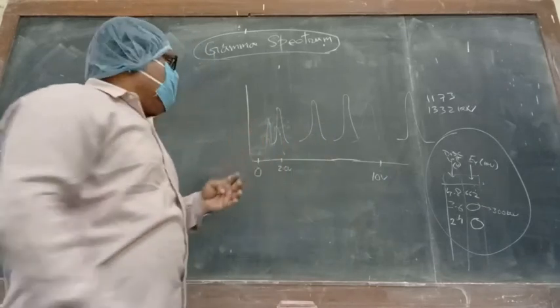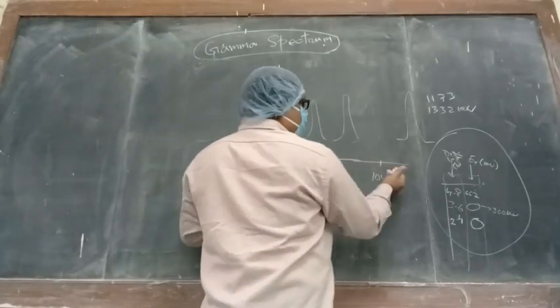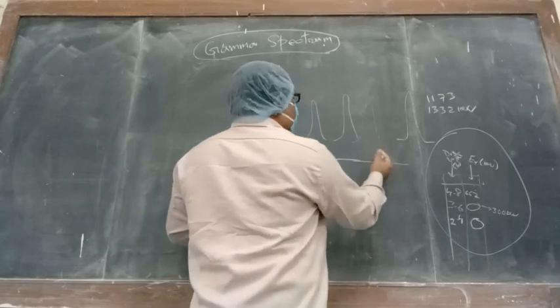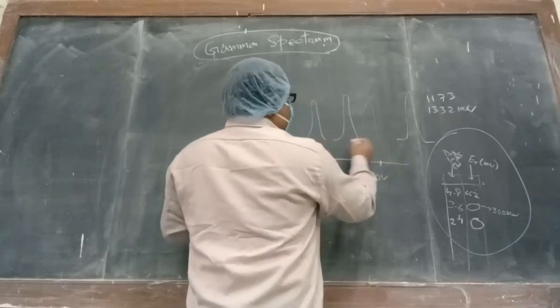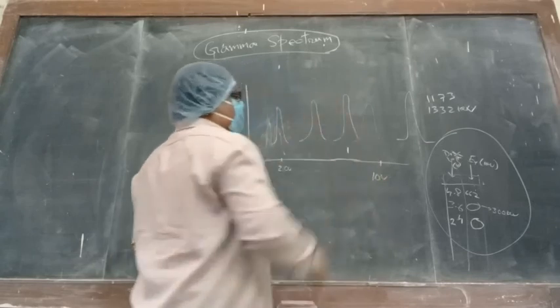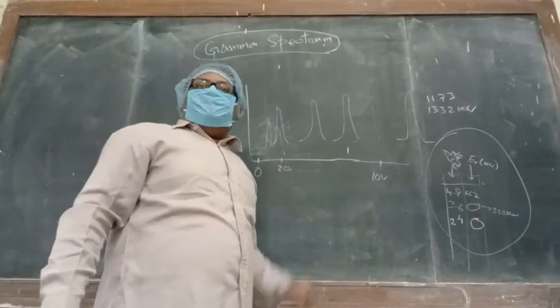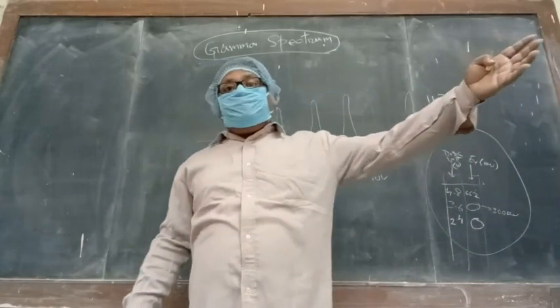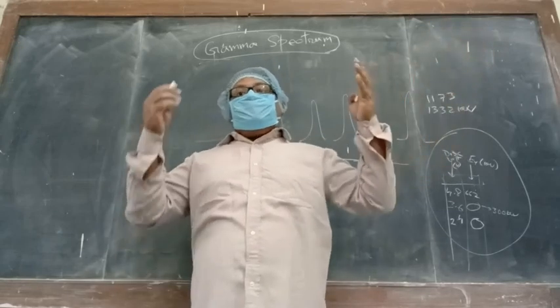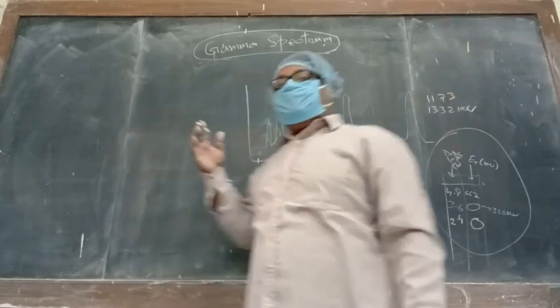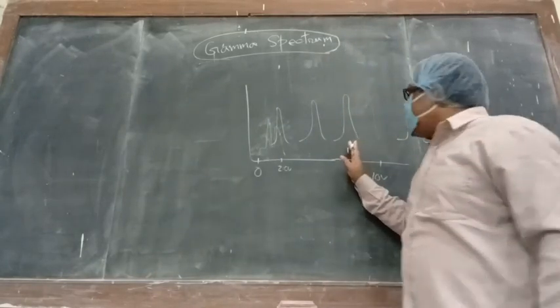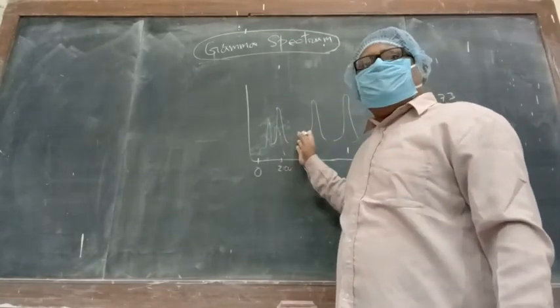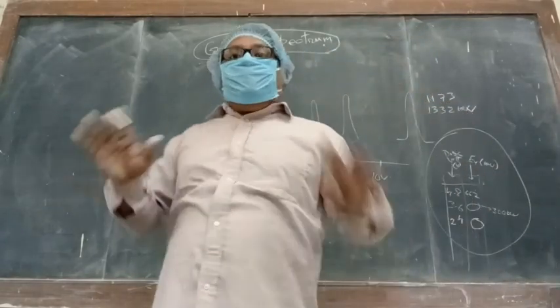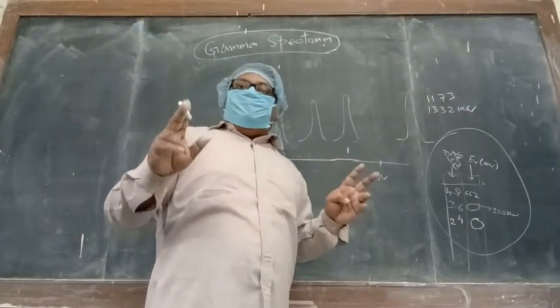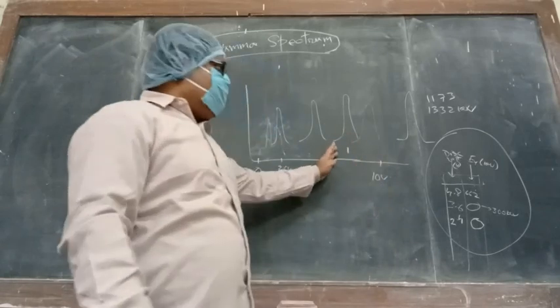Do the experiment. We will have to change the gain of the linear amplifier so that we get the 1332 peak at a standard position, say for example at 8 volts. So this is the reason for setting the gain at 2 volts. I have set it. You can even do the practical yourself and check that by setting the gain at 2 volts, you can get 1332 around that. And as a result, 662 you will get around 3 to 4 volts. So everything is okay. You get the desired full energy peak in your spectrum. You can observe it.